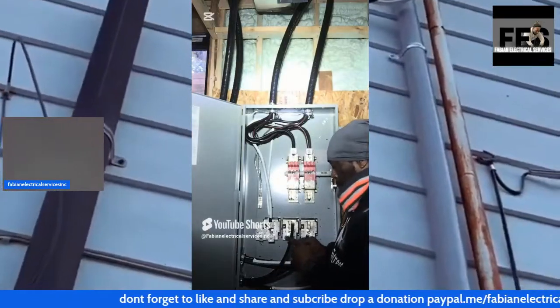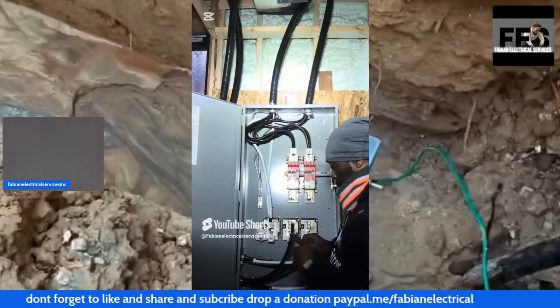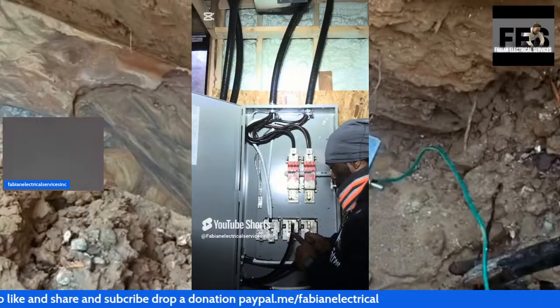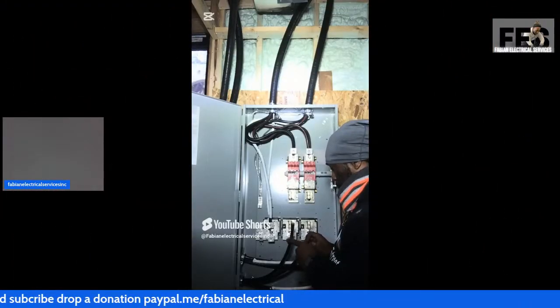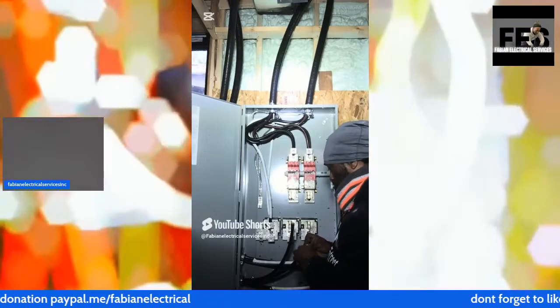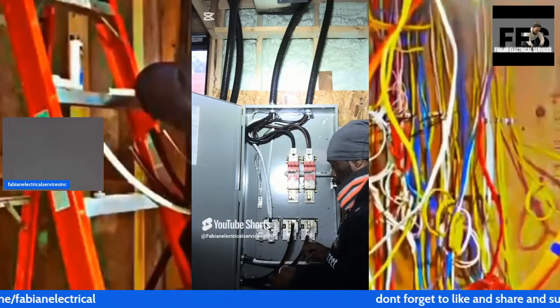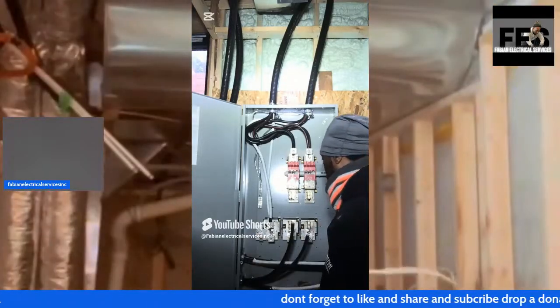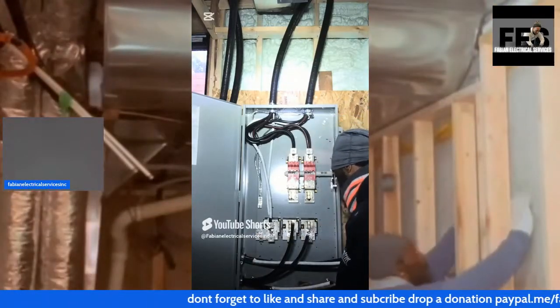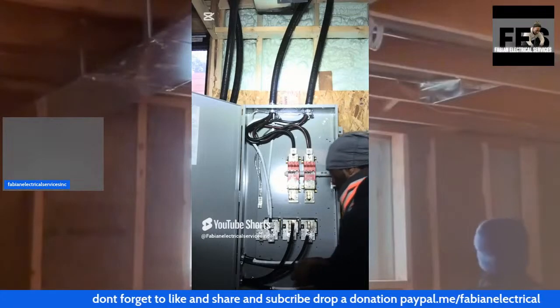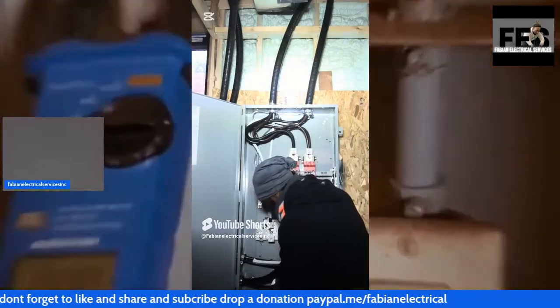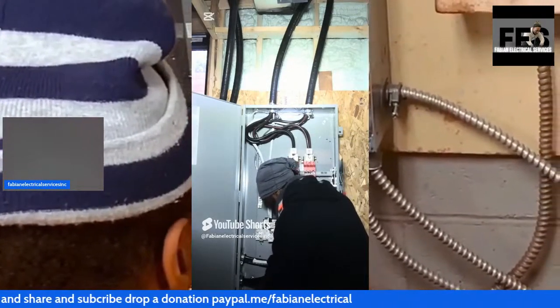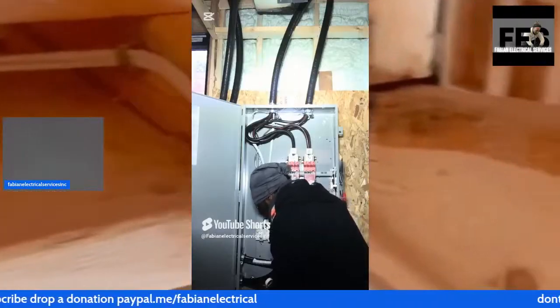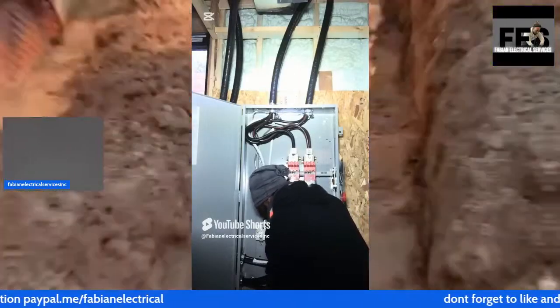Parallel runs is the set of cables you'll see coming in from the top, and that's the line side. The bottom side is the load side. It's always important to make sure your grounding is tucked way on the back side so there's no arcing when it comes to the main components. Also always make sure the line and the load are not touching each other when it goes into the disconnect.